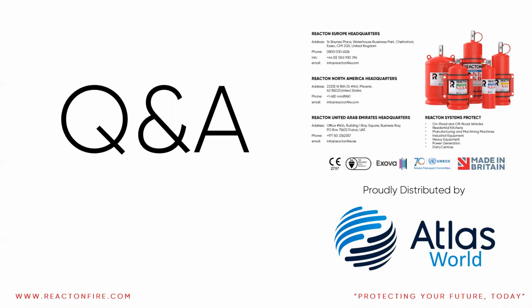So the first question we had in was, what types of gas are used in the systems? So Ed has said there that it depends obviously on the application, but the gases utilised will be 3M Novec 1230 fire protection fluid and Chemours' FM-200 suppression. All systems are super pressurized with dry nitrogen. Correct. Yep. So those are the clean agent systems that I talked about.